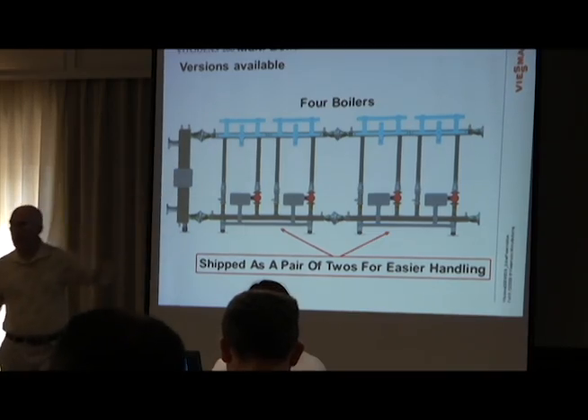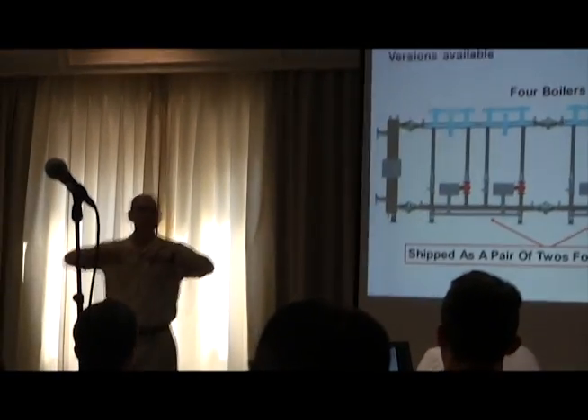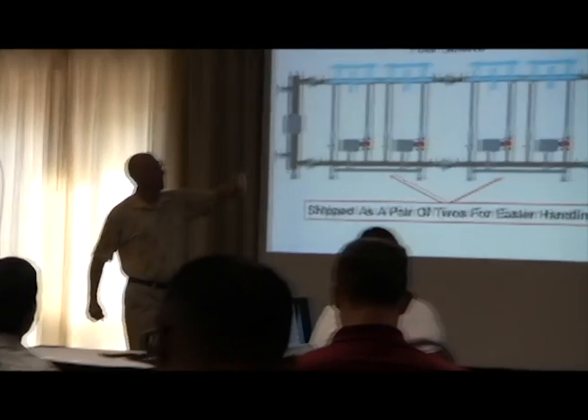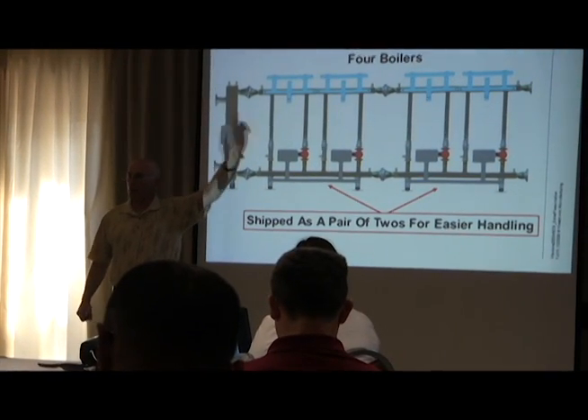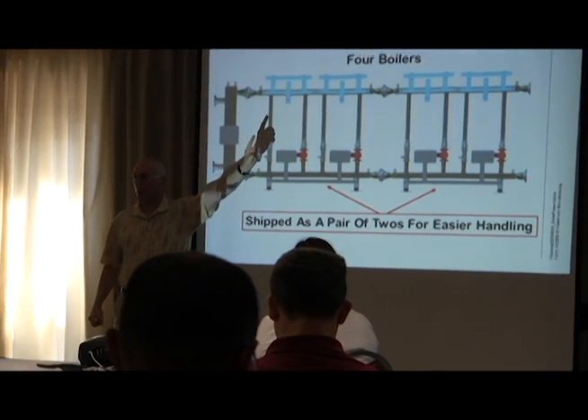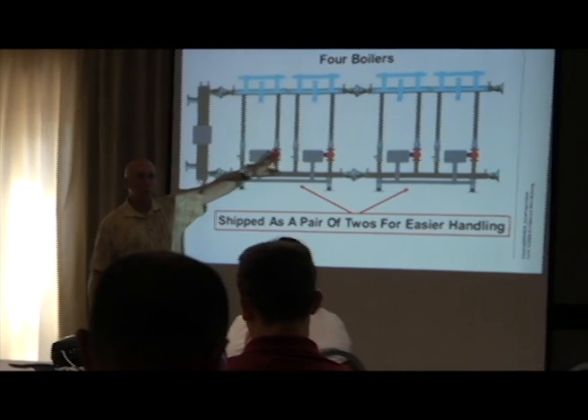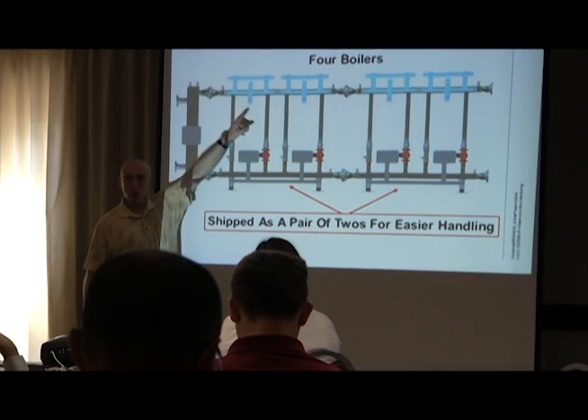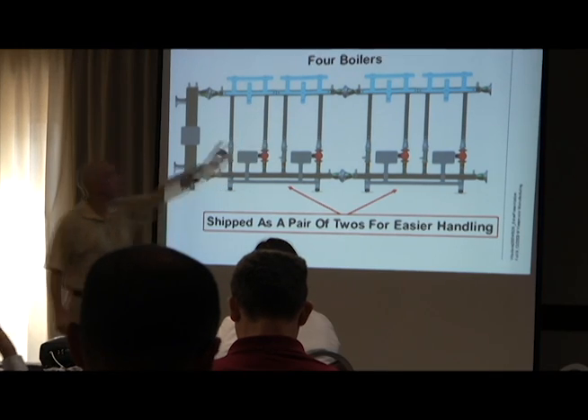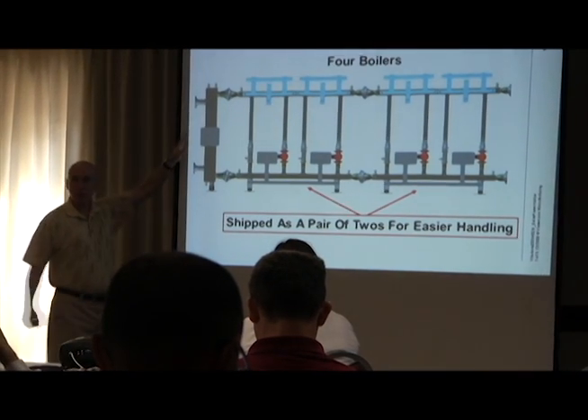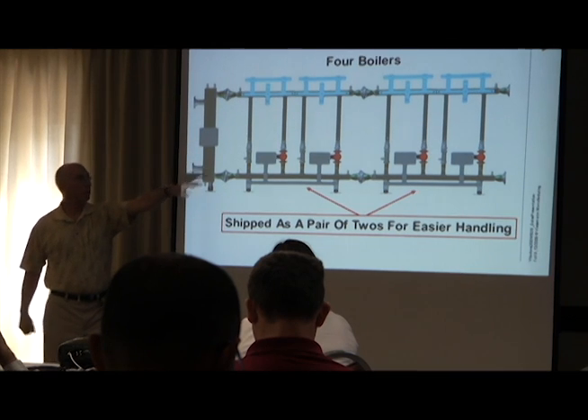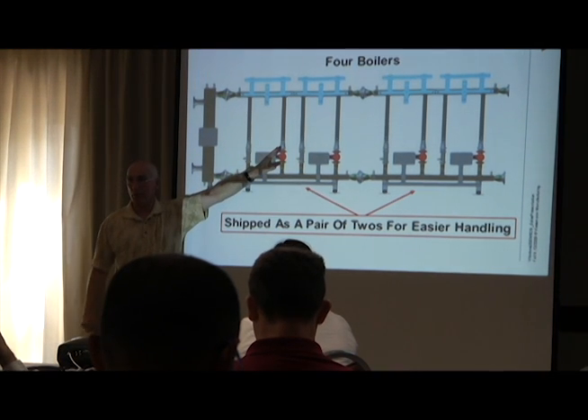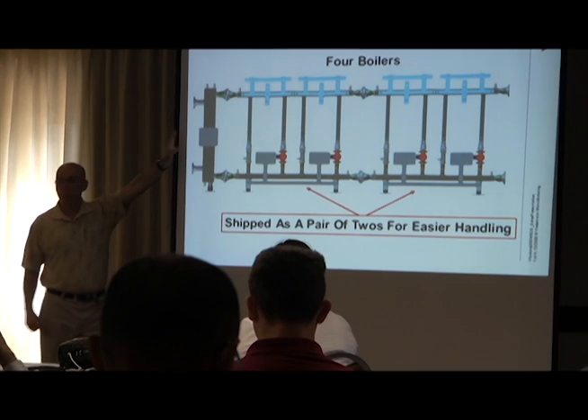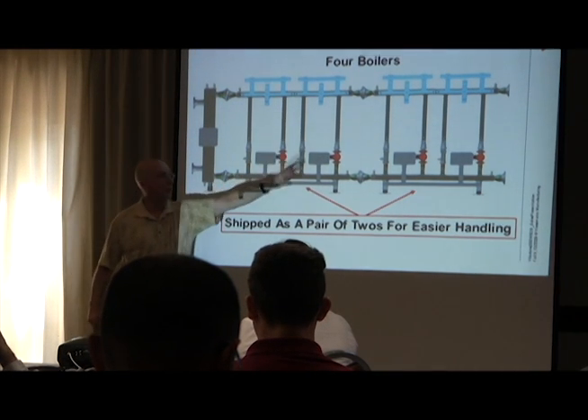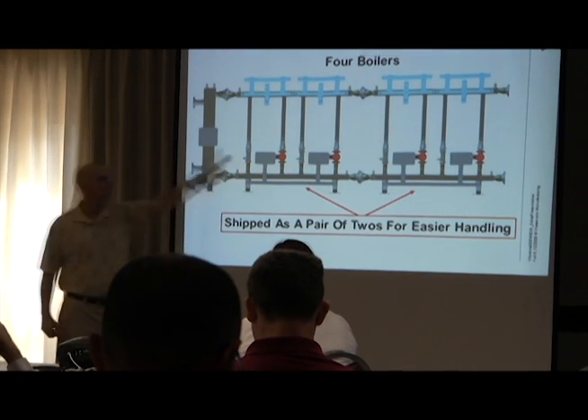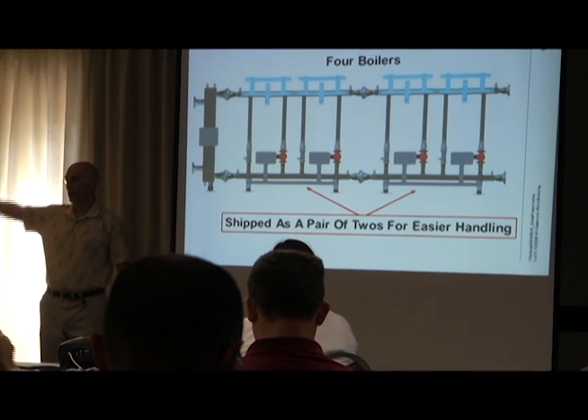But what it does, it decouples the flow rates, because the boilers have a maximum flow rate through the heat exchanger. You can size your pump here so you don't exceed the flow rates through the boiler. Let's say you need 100 GPM over here. Your boiler flow rate is 22 GPM. You can put your 100 GPM pump over here and your 22 GPM pumps on each individual boiler, and it doesn't interfere with any flow rates you got on the other side.